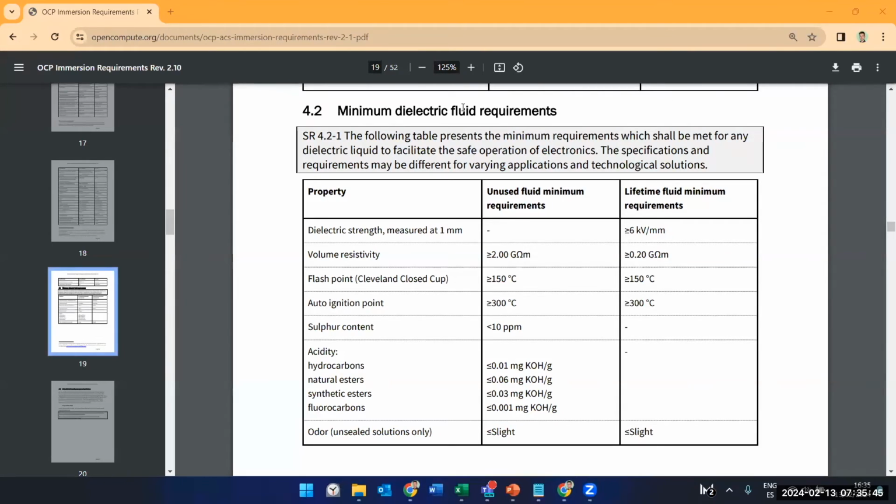So with that said, I think Samantha Yates was the next one with the hand up. Yeah, I want to add, as a component vendor with a large variety of different materials that aren't enveloped in the tables that we have, because you can't account for them. The one really huge piece of data that's missing, that is not even really being collected and is very difficult to collect, is the impact of all of the materials that we put into the fluid from the servers, and the impact of that contamination on the degradation of fluids.